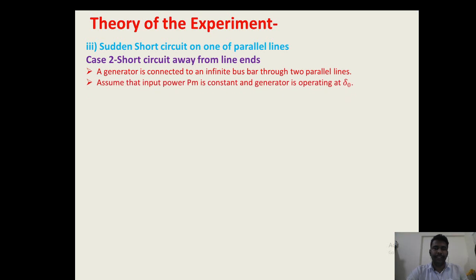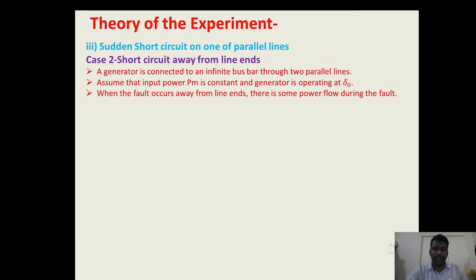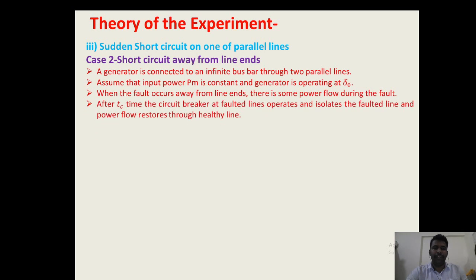We will assume the mechanical power input to the generator is constant, and initially the generator is operating at initial power angle delta_0. When the fault occurs, the power flow through the transmission line is not equal to zero. After the fault is cleared and circuit breakers operated, the faulted line is isolated from the system and power flow is again restored through the healthy line.